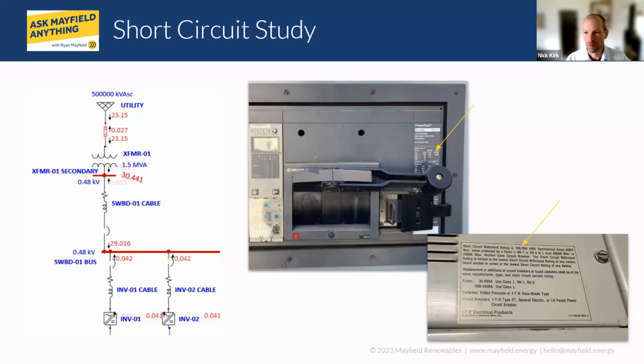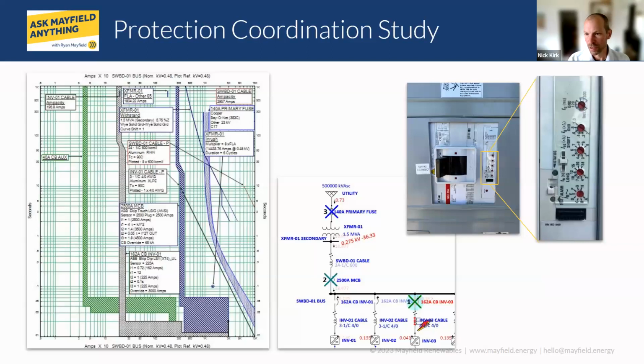The next study was the protection coordination, and this is maybe a topic that may be a little outside of some PV developers' realm, and so I thought I'd just include the NEC definition. And so this is a localization of an overcurrent condition to restrict outages to the circuit or equipment affected, accomplished by the selection and installation of overcurrent protective devices and their ratings or settings for the full range of available overcurrents. It goes a little further, but I think that kind of captures what we're trying to do here. We're basically trying to prevent a fault that's lower down in the system from interrupting unrelated parts of the facility, essentially.